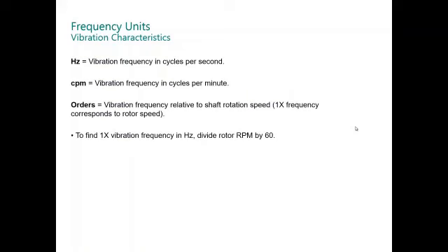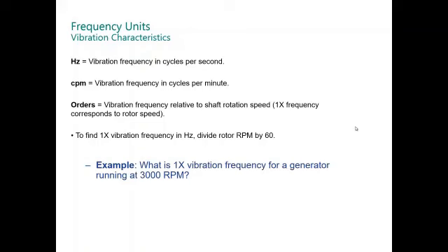The different units for frequency are: frequency expressed in hertz or cycles per second, CPM in cycles per minute, or vibration expressed in orders relative to the rotation speed. One X means the vibration at running speed. To find the one X vibration frequency in hertz, divide the RPM by 60. If your machine is running at 3000 RPM, 3000 RPM divided by 60 is 50 hertz.